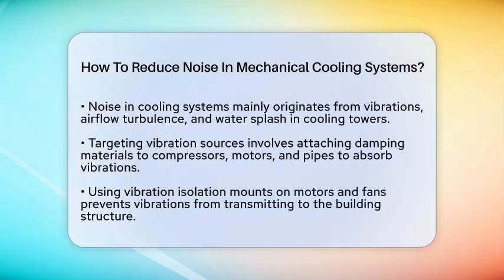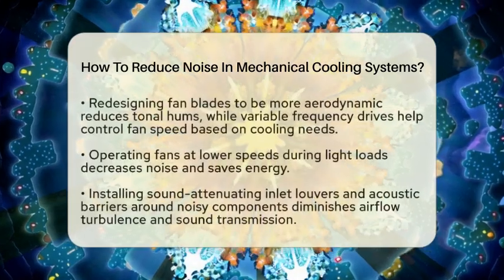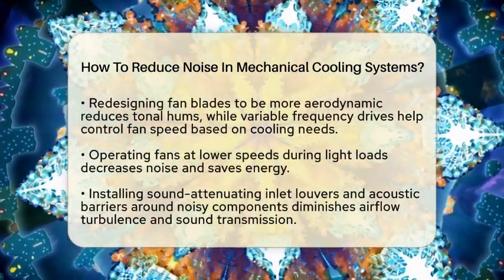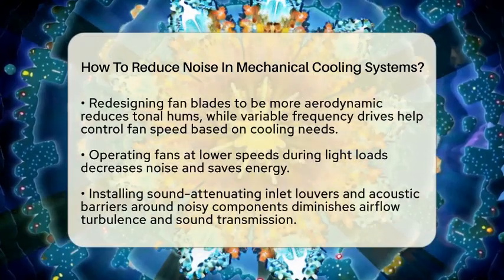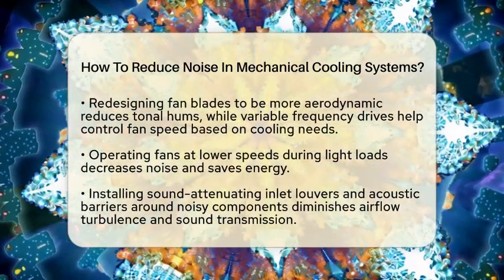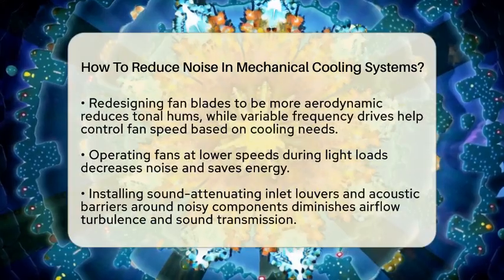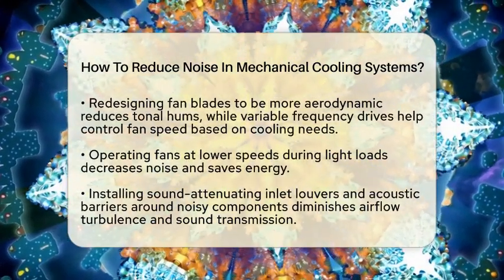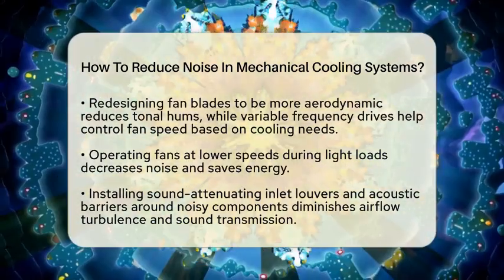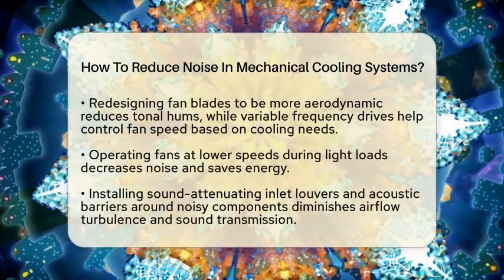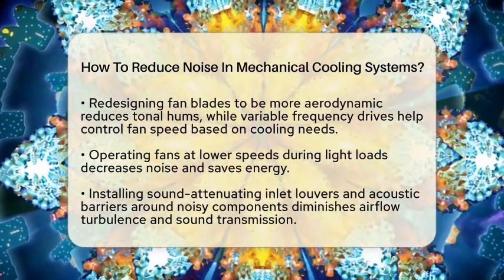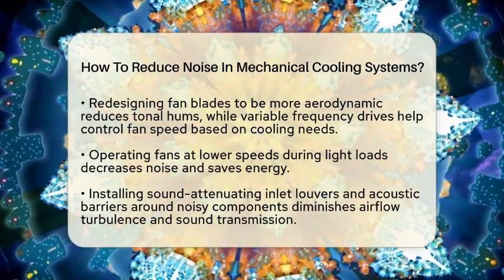One effective way to cut down vibrations is to use vibration damping and isolation. This means attaching damping materials to the surfaces of compressors, motors, and pipes. These materials absorb vibration energy and stop it from traveling through the system. You can replace thin metal panels with thicker, sound-damped versions or add damping layers to existing panels. Also, installing vibration isolation mounts on motors and fans prevents vibrations from reaching the building structure, which reduces noise.